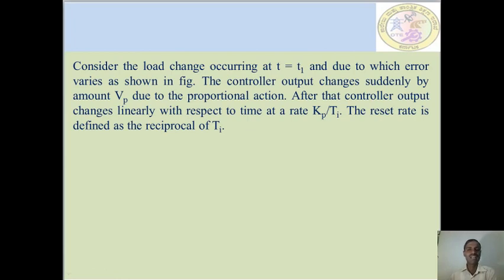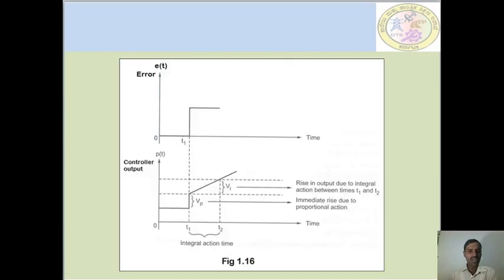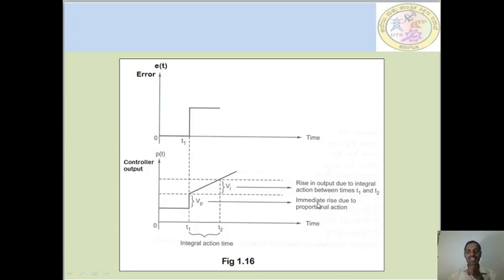After that, the controller output changes linearly with respect to time at a rate Kp/Ti. The reset rate is defined as the reciprocal of Ti, as shown in this graph where error e(t) over time increases both vertically and horizontally from t1. The controller output p(t) over time is also shown. Between times t1 and t2, Vp corresponds to the immediate rise due to proportional action, and Vi shows the rise in output due to integral action.